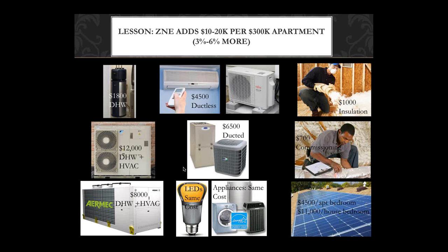Below that, the $12,000 is a Daikin Altherma, and there's a similar product called the Aermec ANK. These use compressors to heat water, and that water, chilled or heated, is used for air conditioning or space heating and domestic hot water. They combine the systems with one set of compressors, but the controls are expensive — about $1,500 of the cost is controls to switch from heating to cooling, which actually makes it a more expensive system. You'd think combining everything would save money, but it makes it more expensive, not less.